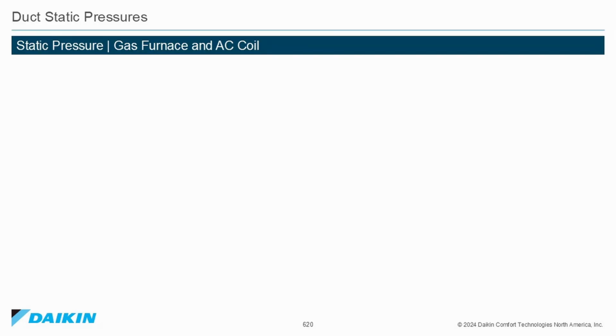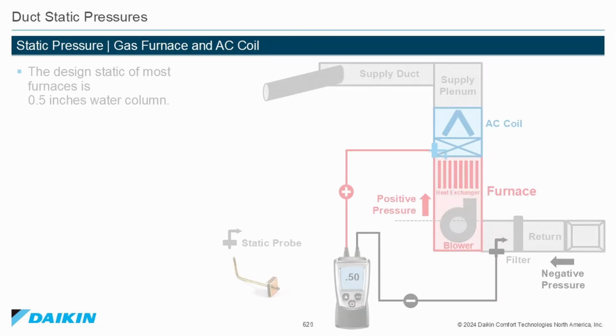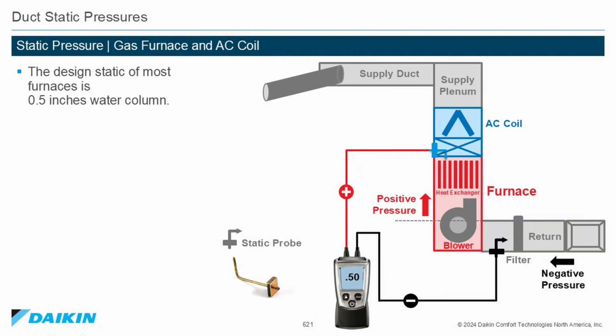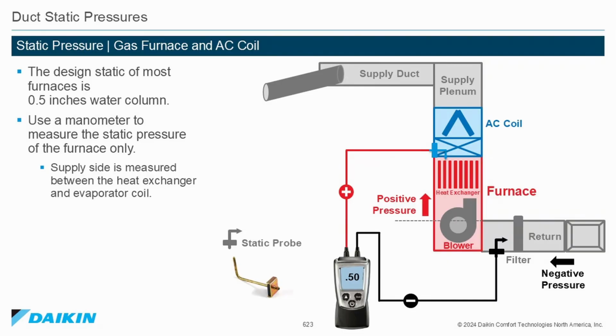Static pressure on a gas furnace and AC coil. The design static of most furnaces is 0.5 inches of water column. Use a manometer to measure the static pressure of the furnace only. Supply side is measured between the heat exchanger and the evaporator coil. Return side is measured between the blower wheel and the air filter.